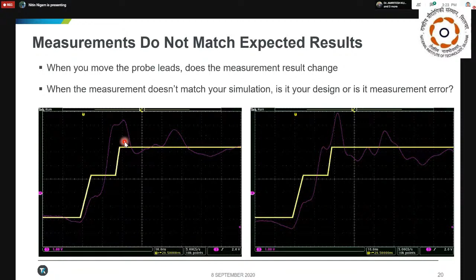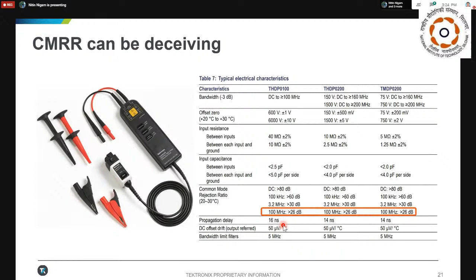For 100 megahertz, we can see the common mode rejection ratio is greater than 80 dB at DC, or 60 dB when it hits 100 kilohertz. But when we are working on gallium nitride and silicon carbide based devices, you need a better common mode rejection ratio, because if you want to do a low side and a high side measurement, common mode rejection ratio becomes a very critical factor, and this value needs to be much, much higher.